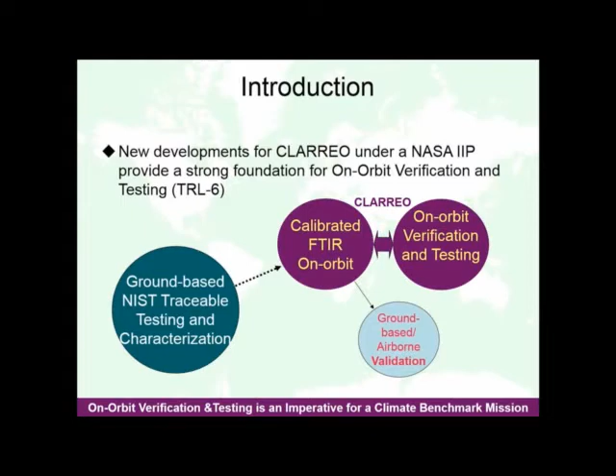So I'm going to talk now about what the system is comprised of, and the main feature is what's called an independent radiance source called the on-orbit absolute radiance standard. It can be run at several different temperatures to check system linearity and as an absolute check on how well your calibrated interferometer is making its measurements.